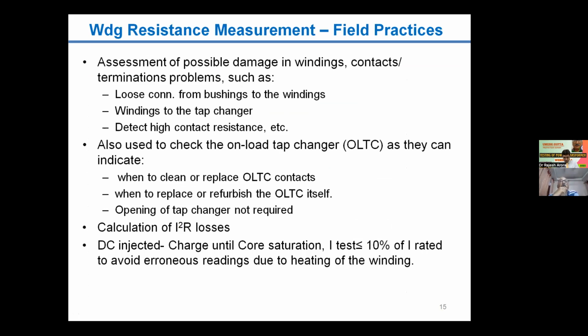So the next test is winding resistance measurement, which we do in the field, and this is a very important test. In earlier days, as I remember when I started my career, these kinds of tests were not there. We were testing open circuit, short circuit and Megger, insulation resistance, etc. And then charging the transformer.